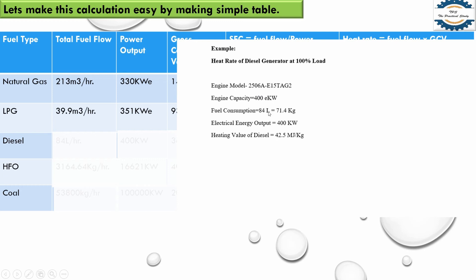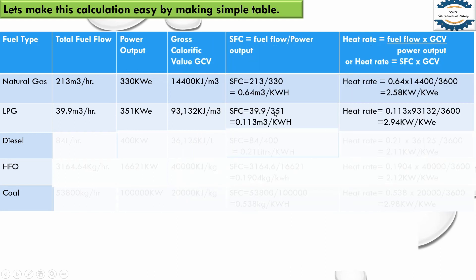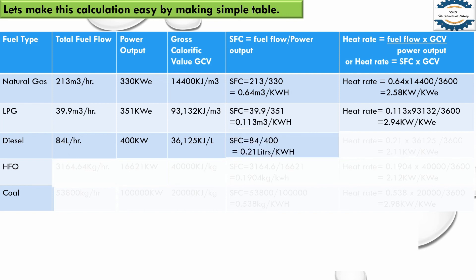For diesel, I selected a diesel engine model 2506A. Its engine capacity is 400 kilowatt and its electrical energy output is also 400 kilowatt. Fuel consumption is 84 liters per hour, or 71.4 kg per hour. The GCV of diesel is 36,125 kilojoule per liter. Similarly, for specific fuel consumption we divide fuel flow by power output, and for heat rate we multiply specific fuel consumption by GCV and divide by 3,600.